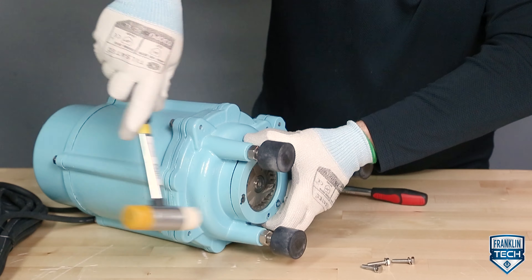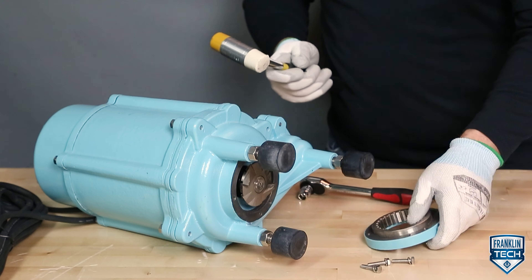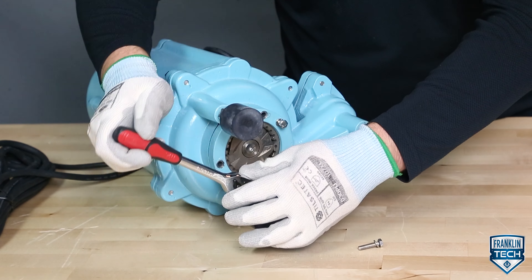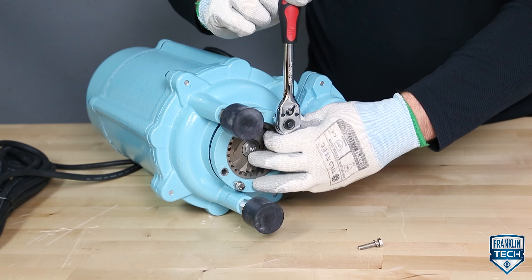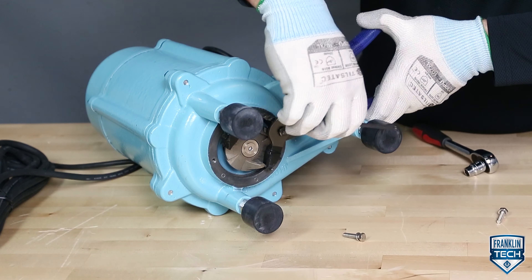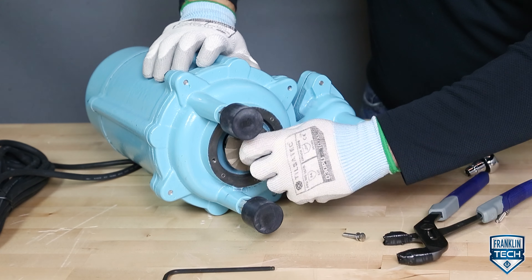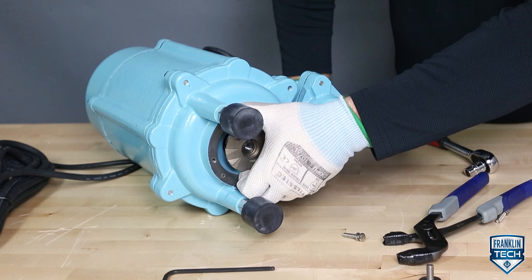Lightly tap the stationary cutter assembly with a rubber hammer to remove it from the volute. You can also use the M6 bolts as jack screws on the cutter assembly. Remove the impeller bolt and washer with a 5 mm Allen wrench or hex head socket, being careful not to damage the rotating cutter. Use channel locks to hold the rotating cutter to keep it from spinning, then remove the rotating cutter from the motor shaft.